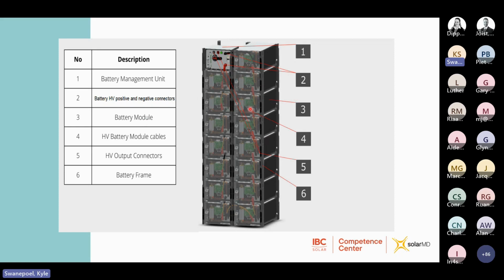Then number 3 is a battery module, which we've just covered. And then the HV battery module cables. That is your interconnecting cables. The solution is provided with color-coded cables to make it easy to connect. You'll have one positive to positive connection, which comes from the BMU to your first module, and then negative to positive connectors to connect all of the modules in series. You have a longer cable to go from the bottom left to the bottom right module, which is also negative to positive, and then at the top you have your negative to negative connector, which is also a longer cable. That is supplied with the battery itself.